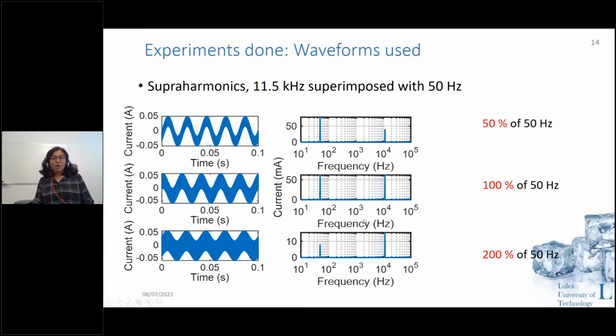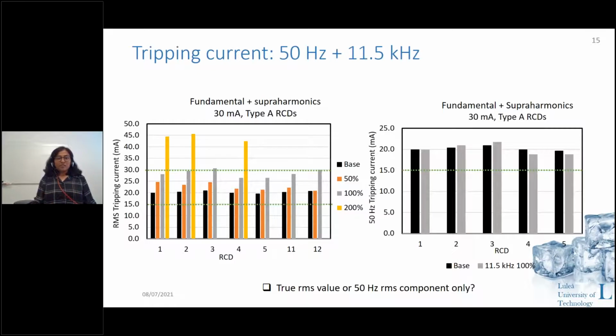When we tested all these 13 RCDs with these 3 waveforms, we get this kind of result. On the left hand side is the RMS value of the tripping current that we got for different cases, and there is a comparison with the base case. So if you see the RMS value, the RCDs are all rated 30 milliampere, which means they should trip somewhere between 15 milliamperes and 30 milliamperes. For 100%, all of these RCDs are still below 30 milliamperes, but the one with 200% is above 30 milliamperes. So you would feel that the RCDs in the case of 200% fail to trip, because they should be tripping somewhere below 30 milliamperes.